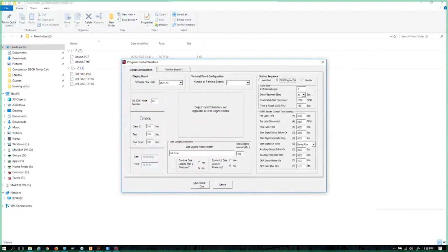So we have the same feature up here about the number of start attempts, and the same thing applies here, obviously. Delay between start attempts, multiple start crank / multi-start disconnect. So again, I have 350 here. And then we have a feature that says time to reach 350 RPM. In this case, I have 160 seconds. So if I don't reach 350 RPM by the time 160 seconds expires, I will fault down out on what we call overcrank. Familiar term, I think, in our industry.